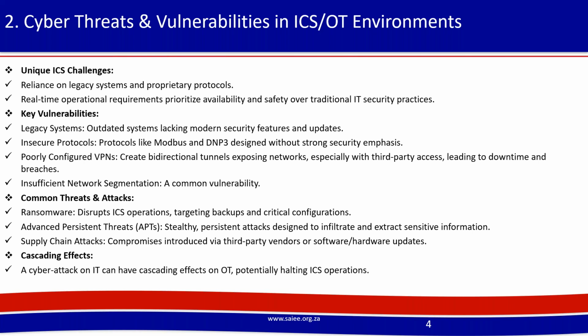The key vulnerabilities, some of the specific vulnerabilities we see include the continued use of outdated systems, which lack modern security updates. I can tell you that there's somebody out there who's using Windows Server 2003 at this very moment. Communication protocols such as Modbus, DNP3, and other serial-based communication protocols, while they are foundational, were designed for functionality and not really security, making them susceptible to exploitation.